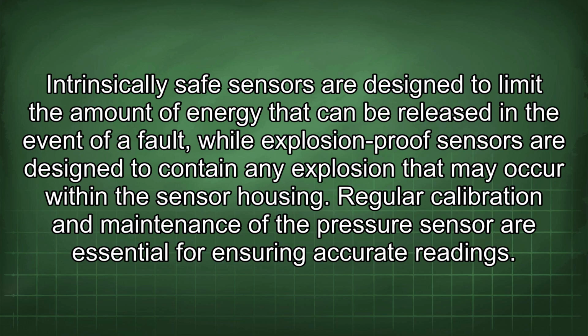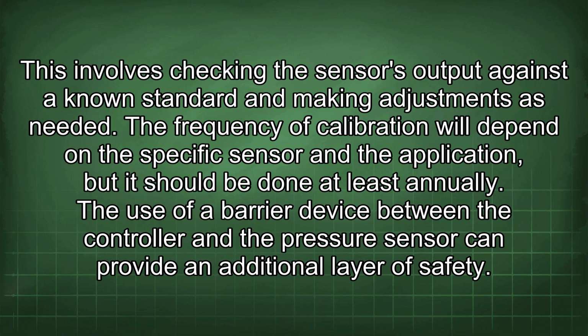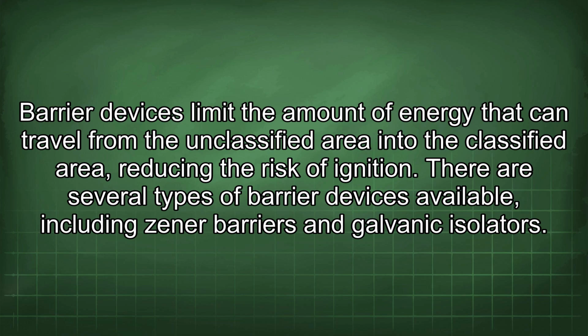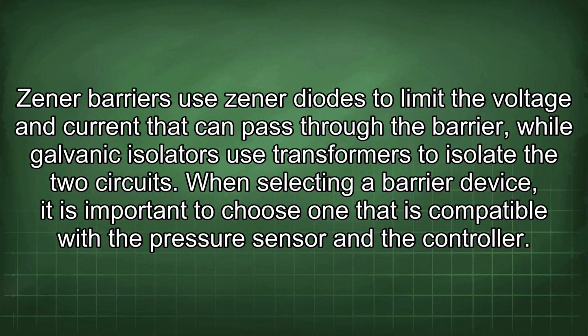Regular calibration and maintenance of the pressure sensor are essential for ensuring accurate readings. This involves checking the sensor's output against a known standard and making adjustments as needed. The frequency of calibration will depend on the specific sensor and the application, but it should be done at least annually. The use of a barrier device between the controller and the pressure sensor can provide an additional layer of safety. Barrier devices limit the amount of energy that can travel from the unclassified area into the classified area, reducing the risk of ignition. There are several types of barrier devices available, including Zener barriers and galvanic isolators. Zener barriers use Zener diodes to limit the voltage and current that can pass through the barrier, while galvanic isolators use transformers to isolate the two circuits.